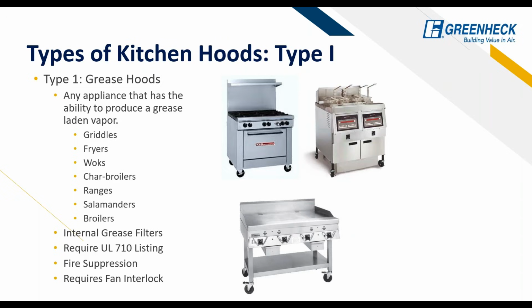So as we get into the kitchen hoods, there's two types of kitchen hoods, and some people get a little confused sometimes about the difference between type 1 and type 2, and all it comes down to is grease applications and fire systems. Type 1 hoods will have a fire system, type 2 hoods will not. So anytime you have grease producing foods, think cheeses, meats, oils, anything that's going to be creating grease, we must put it under a type 1 hood, and it must have a filter and fire system in it.